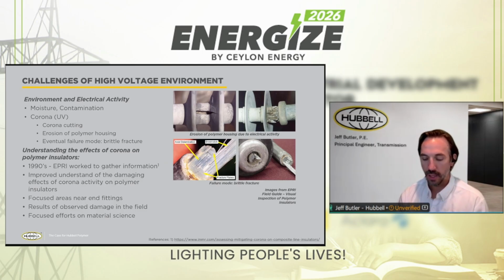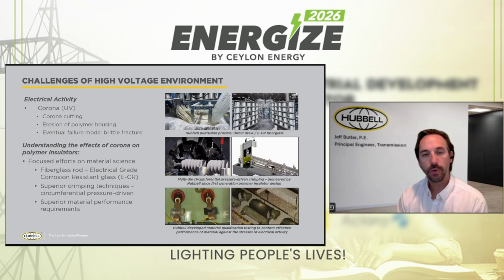So when insulators were first introduced, a lot of these stresses for the insulator were not well understood. So in the 1990s, an organization called EPRI, Electric Power Research Institute, based in the United States, as well as supported with STRI, S-T-R-I, the Swedish Technical Research Institute, combined together to explore in the industry where there were some issues that were occurring with polymer insulators out in the field, where they were experiencing premature failure. In their investigation, what they found was the electrical activity was degrading the insulators primarily at the interface of the end fitting and the rod and the rubber. So where all three of those interfaces come together, as shown in the pictures there, that's where they were seeing the primary number of failures. Now, that's not to say that all polymer insulators were having issues, but those that were primarily were having it concentrated in this area. So that led them to understand certain aspects of the environment for the insulator that were not previously well understood.